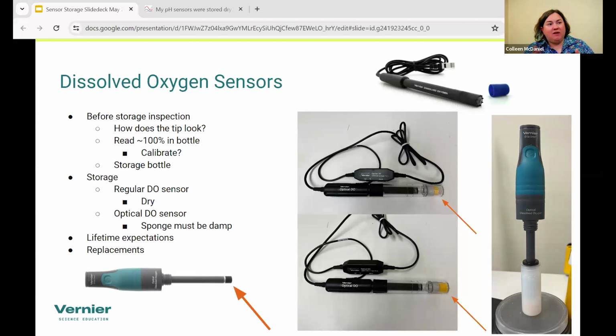You also can check by just putting it in its storage bottle. The optical ones have a storage bottle they come with that is very similar to the ISEs, in that you have a little sponge in the bottom, and you want to make sure that sponge is kept moist. So you want distilled water, but you don't want the probe sitting in the water. What it should be reading in that bottle is around 100% saturation. You don't necessarily have to calibrate it again before storing. I would just check it when you take it out of storage and make sure it's reading around 100%.